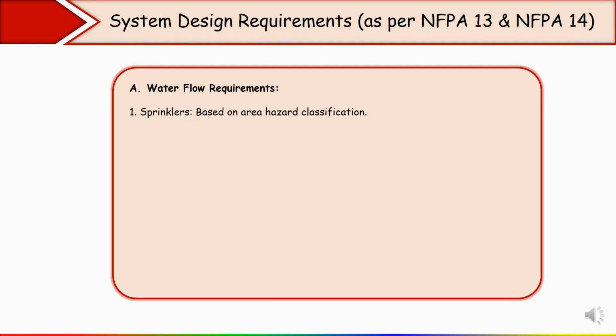See, for sprinkler, based on area hazard classification, you know that in case of light hazard occupancy, 0.1 GPM per square feet over the most remote area of 1500 square feet. This is the water flow requirement for light hazard.